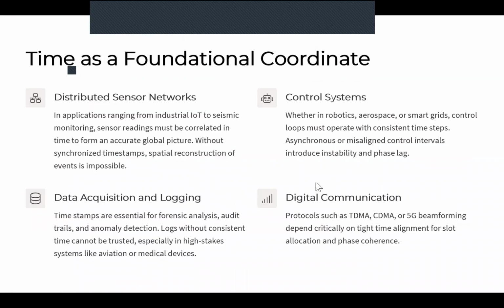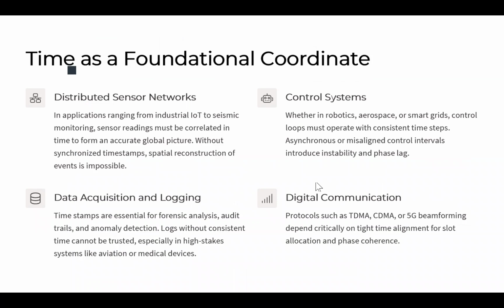Now, let's begin with the concept at the heart of the standard IEEE 1344. The standard's basic message is that time is not just a background parameter, and we have to deal with it like a primary coordinate of our system state. Every physical system and every physical measurement, it doesn't matter if it's a voltage or pressure or a position, exists in the context of when it was recorded. So if the time is not reliable, then it doesn't matter how accurate those measurements are, we cannot trust them.